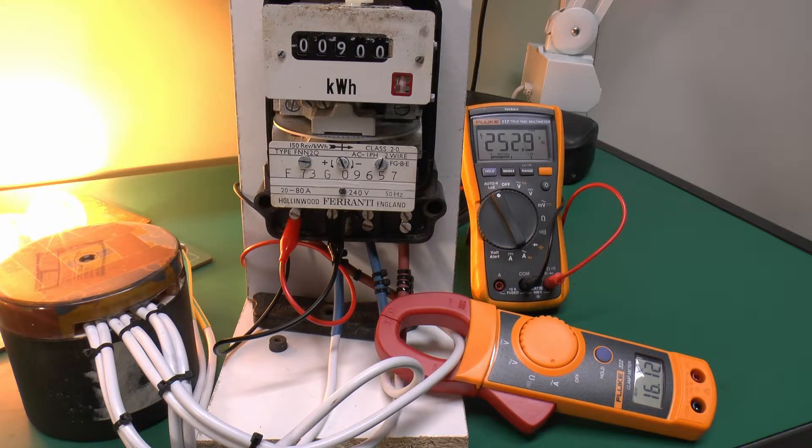The average voltage over the period was 252.9 and the current 16.14 amps. And if you multiply those two together you get 4.08 kilowatts. So virtually identical. So it's highly accurate despite its rusty condition and filth and dirt all over it.